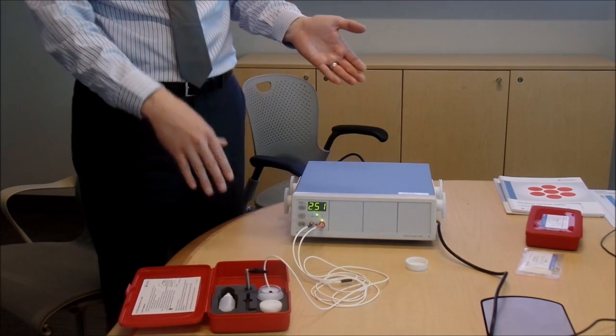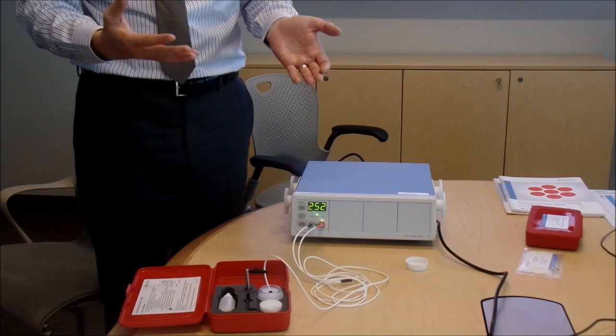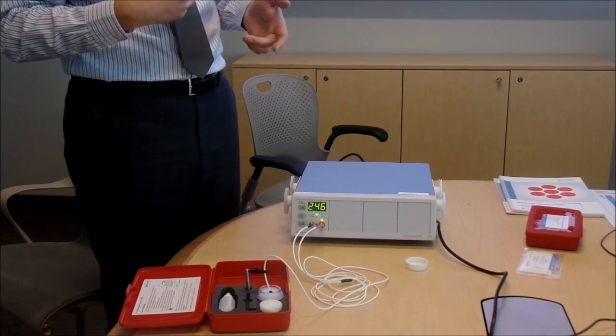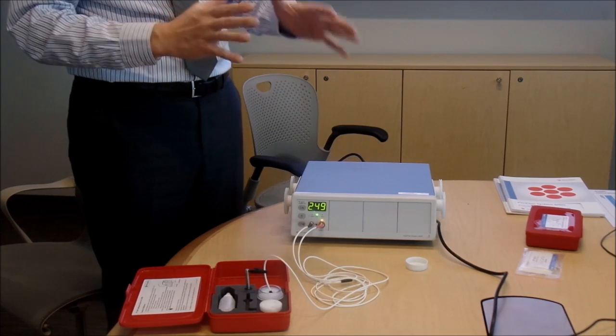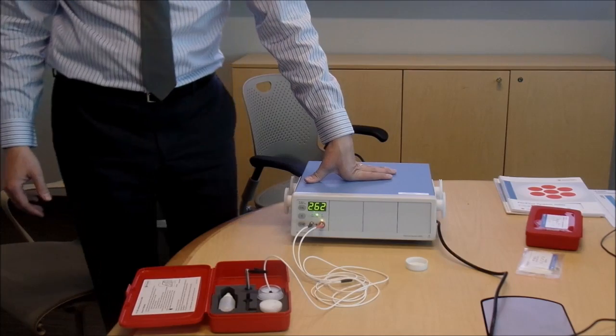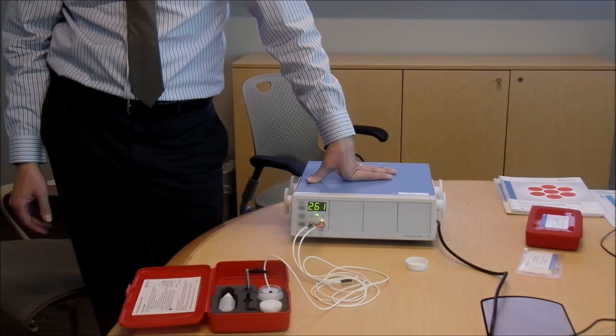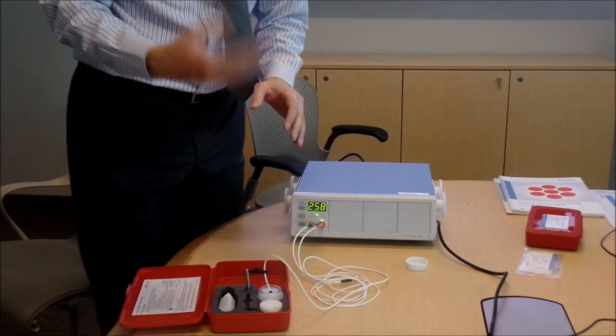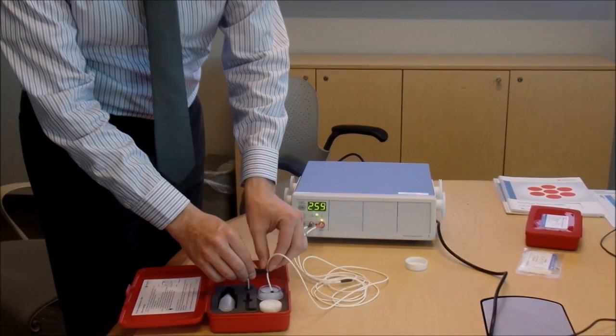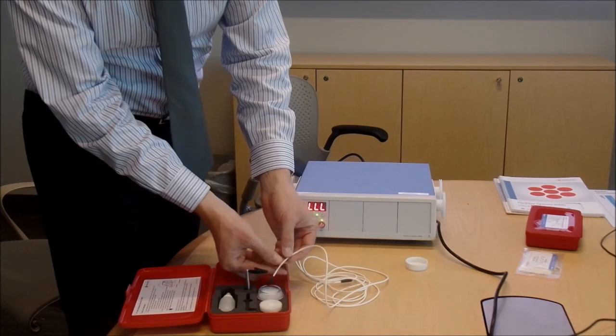And you might find, if you have three probes, two of them read 250, give or take a little bit in the fluid, and one of them reads 95. Now, we might even look at swapping out that probe for a different one, just to get you three that are very similar. And in that case, you probably don't have to calibrate more than twice a year or so. Okay. I think that might probably be the easiest. We can take all four probes and look at them. Yeah. I think we have three right now. And see which one's the outlier.